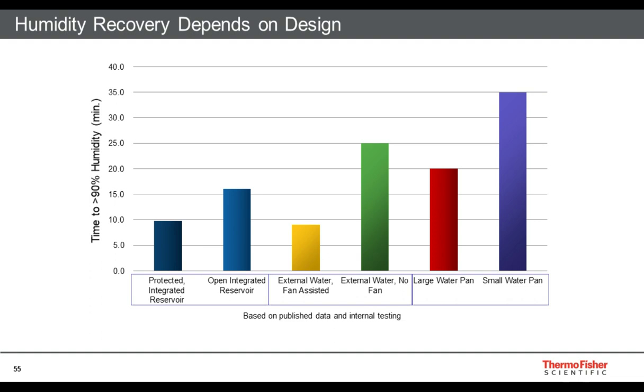The yellow bar is an external water system. And what this is, it's an external water reservoir connected to a nebulizer that creates a water vapor or mist, and that's injected directly into the incubator chamber. And that's really fast to recover as long as you have a circulating fan to speed that recovery and that circulation following a door opening and following injection of the atomized water. And you can compare that to the green bar to the right of that yellow bar, which is a similar but different system in an incubator without a circulating fan. And then the last two bars, the red and the purple, just compare surface area of a traditional standard water pan used to provide passive humidity in an incubator.